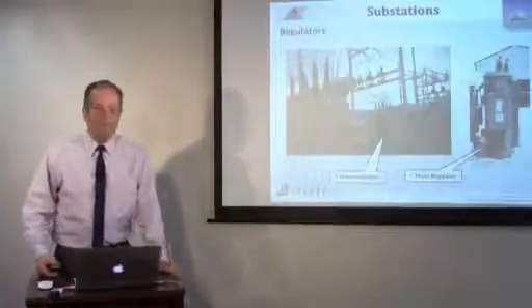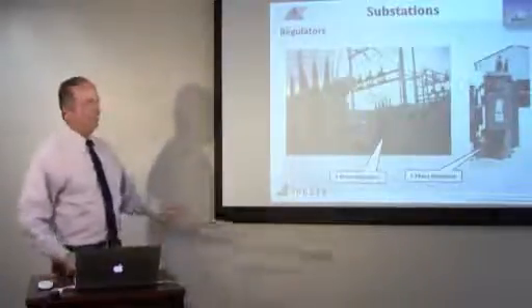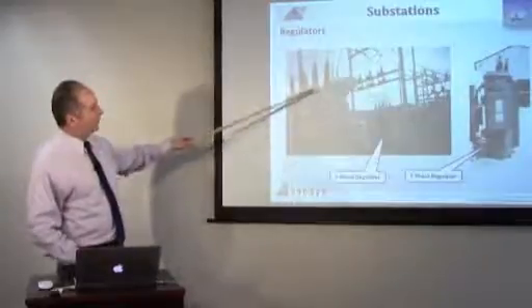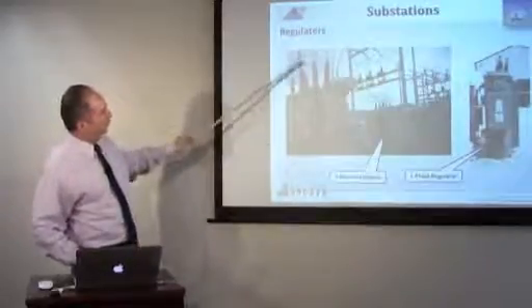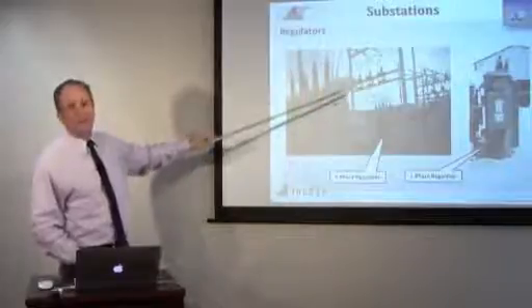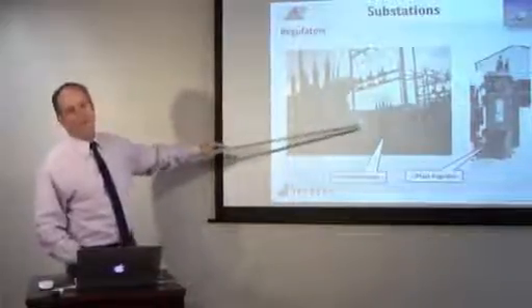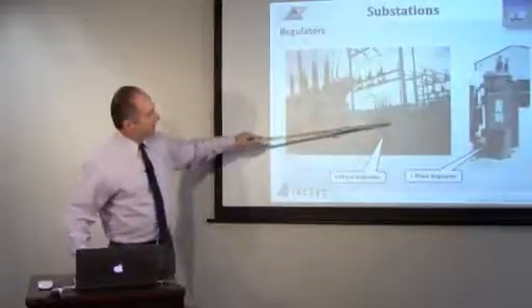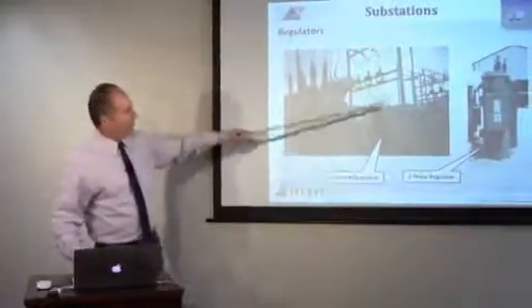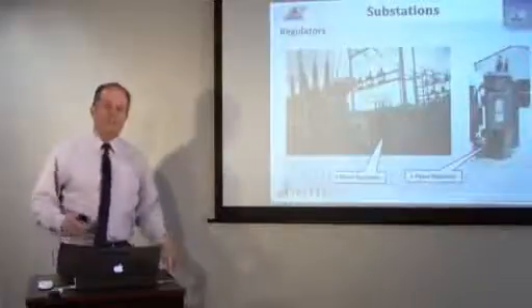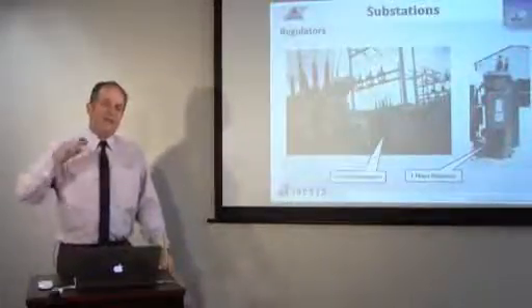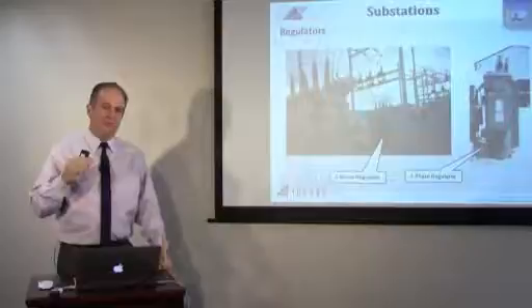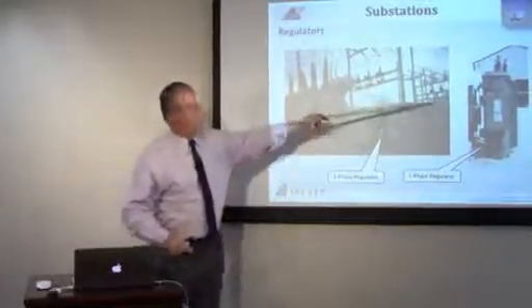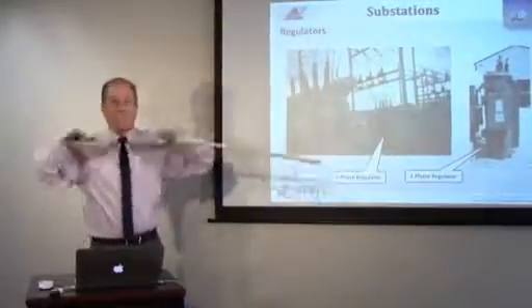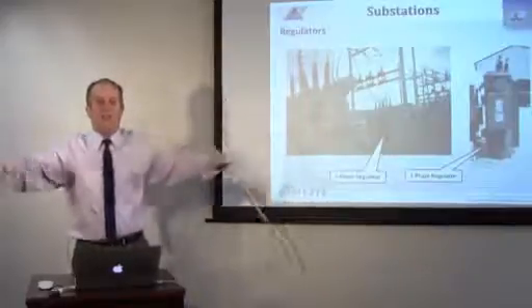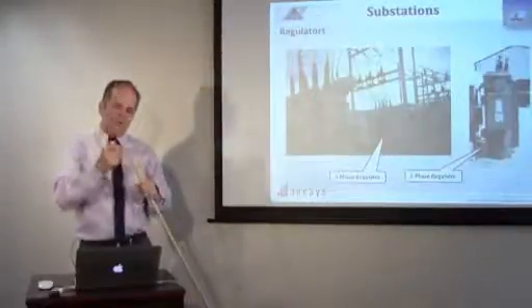Okay, let's talk about regulators. In the case of regulators, what we're trying to do here is take a regulator. Here's a transformer that's taking like 69 kV down to 12.5 kV. So it's a distribution substation. Here's a regulator. This is a 3-phase voltage regulator. And what it does is it takes the secondary voltage and controls it plus or minus 10%. Then all of the circuit breakers and all the feeders, all the distribution lines off of that regulator are all controlled by that source voltage.